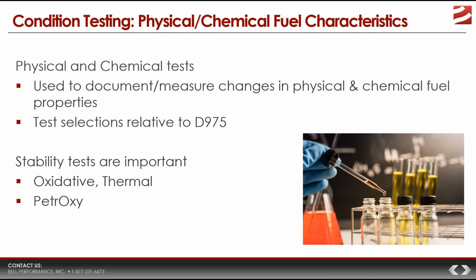We also know, however, that microbial contamination changes the physical and the chemical properties of the fuel in certain ways. Things like total acid number of the fuel, the peroxide number, the fuel's viscosity, those can all be increased by the effects of microbial contamination, while other things like cetane value and stability ratings can be reduced.